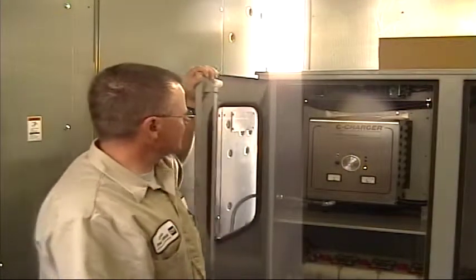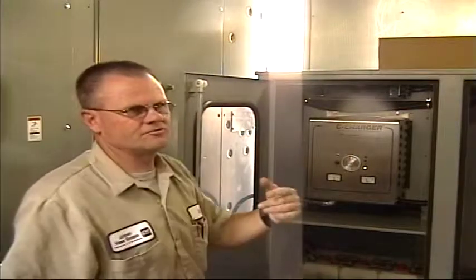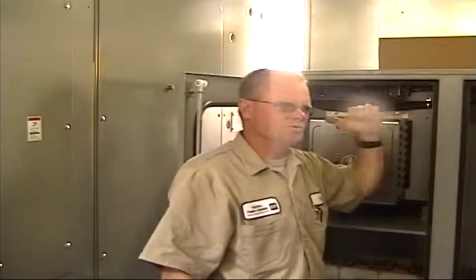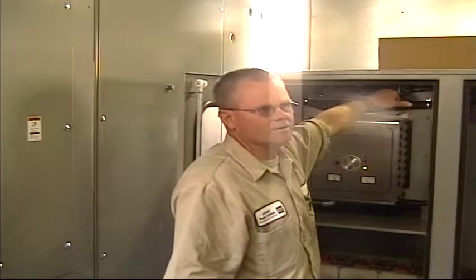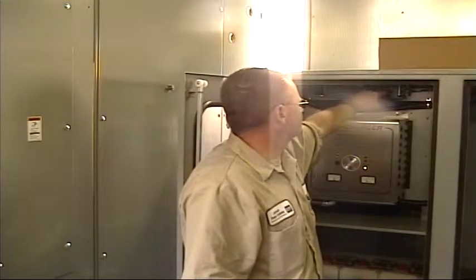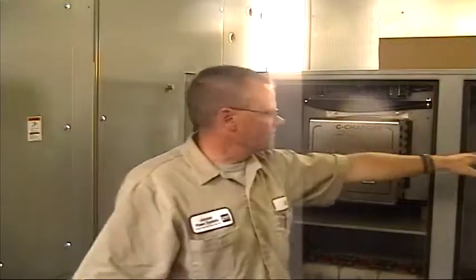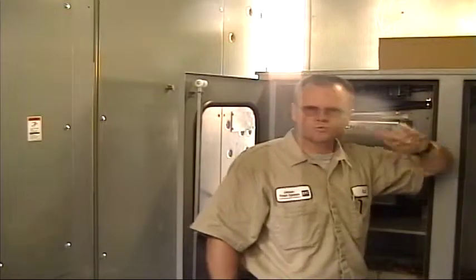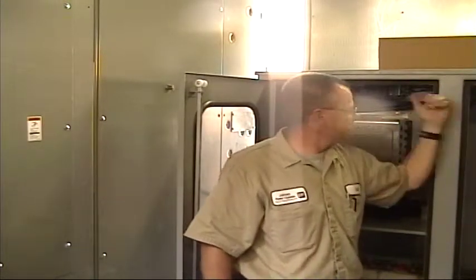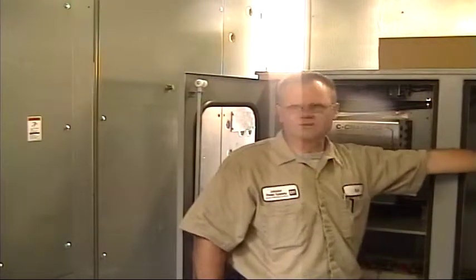One of the status lights you can look at to verify if you're sending 48 volts to your switchgear is a little green light up here. There are status lights that will tell you if there's any fault indications up here. There are some fuses up here for the switchgear, and fuses for this converter. They're all located on this side of the panel.